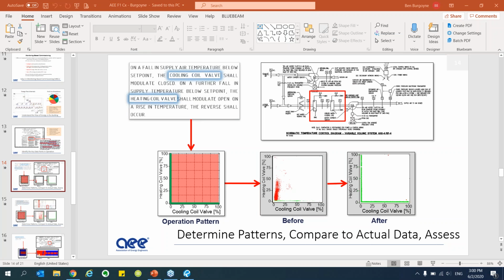But if they're reversed, which is rare. Usually, if you have dehumidification in the air handling unit, you'll have two heating coils, one before the cooling coil and one after the cooling coil. And that's the reheat for when you're doing dehumidification. And I'm thinking if you have, for example, cooling on full blast and then you're adjusting a reheat coil, then that's going to make for over dehumidification of your space. Essentially, you have dehumidification running more than it should.